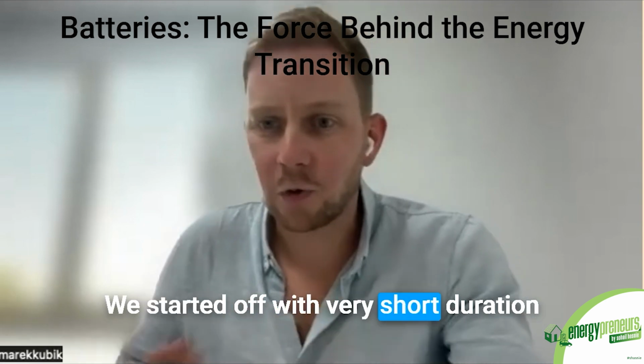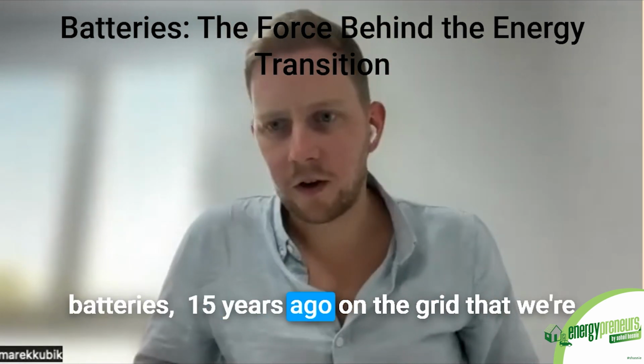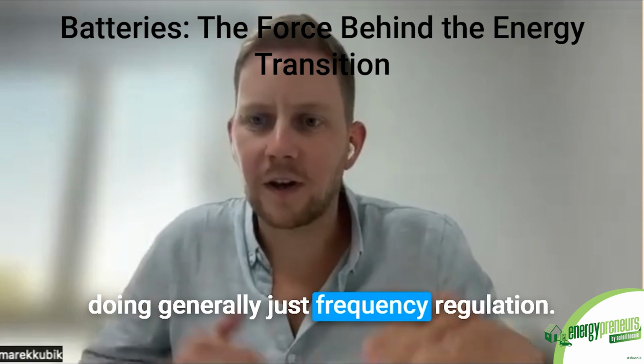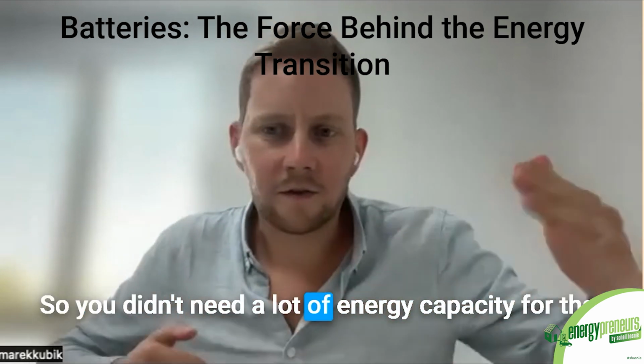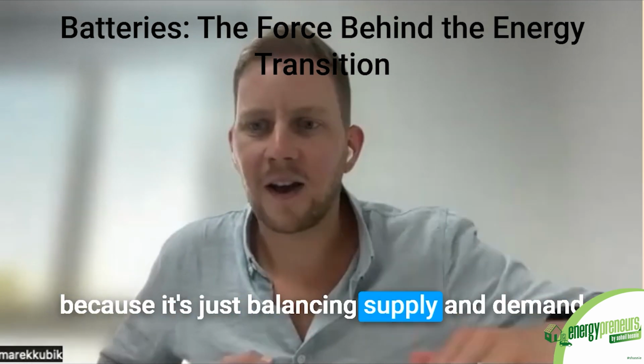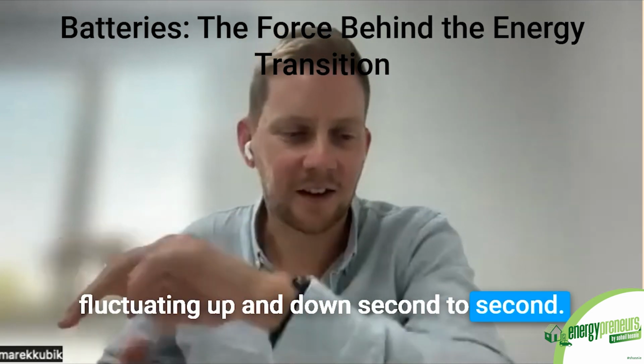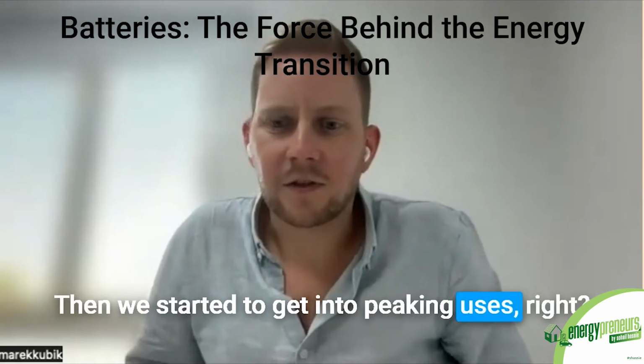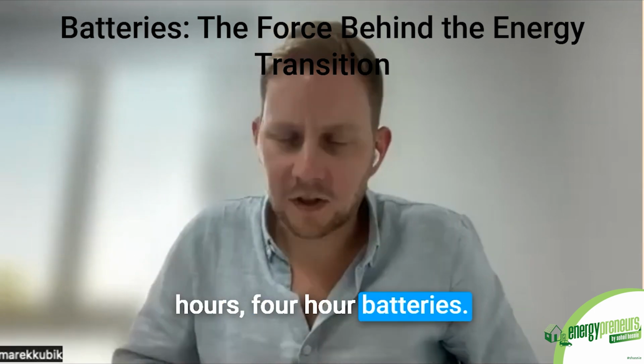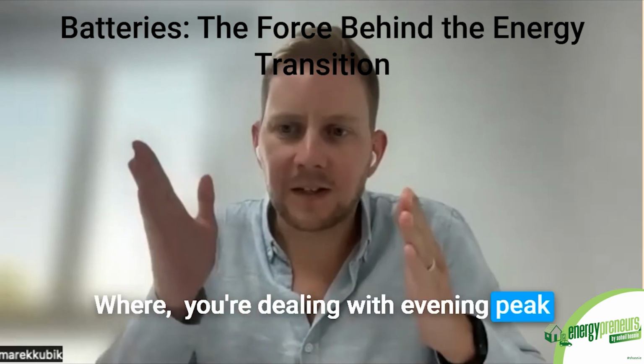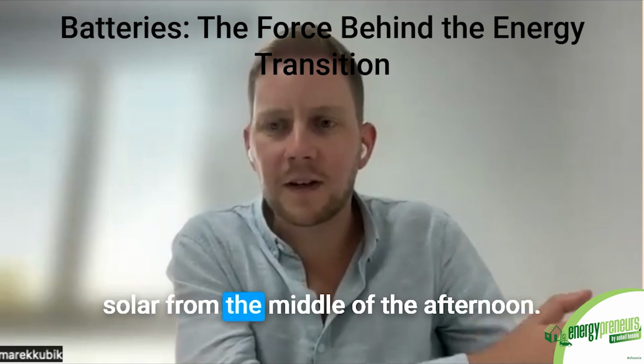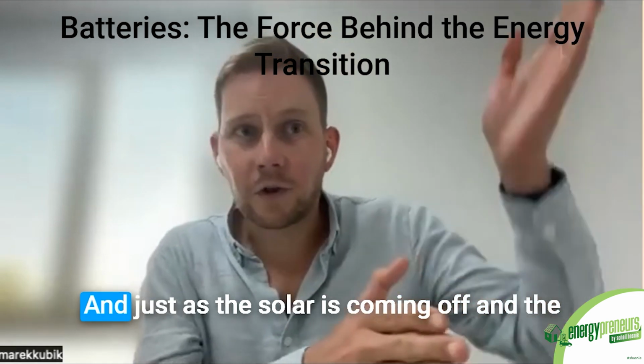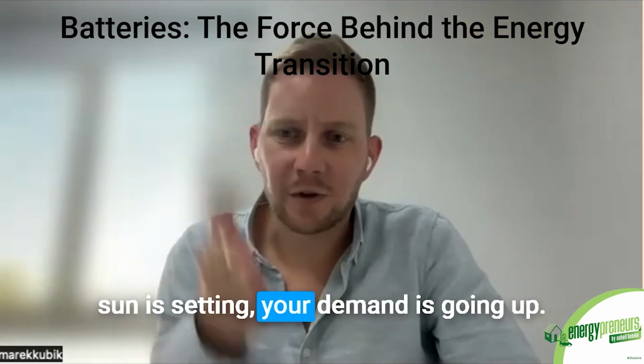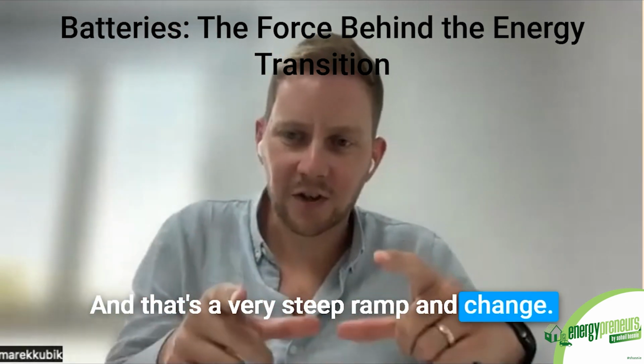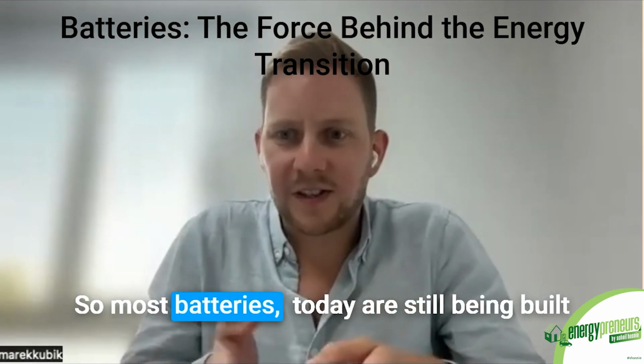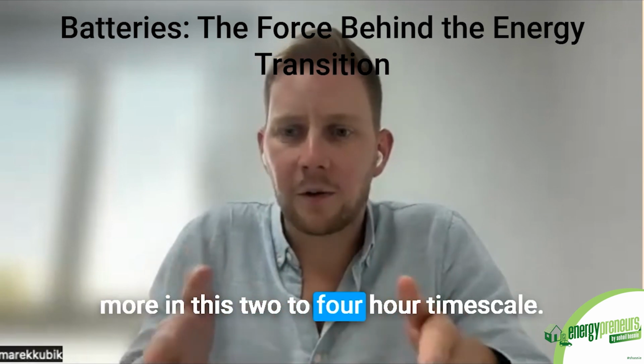We started off with very short duration batteries 15 years ago on the grid that were generally just doing frequency regulation, so you didn't need a lot of energy capacity since it's just balancing supply and demand fluctuating second to second. Then we started to get into peaking uses, seeing 2 hour, 4 hour batteries dealing with evening peak demand, for instance shifting solar from the middle of the afternoon. Just as the solar is coming off and the sun is setting, demand is going up, and that's a very steep ramp and change. So most batteries today are still being built more in this 2 to 4 hour time scale.